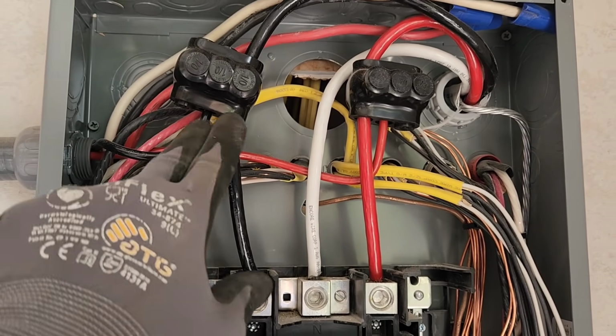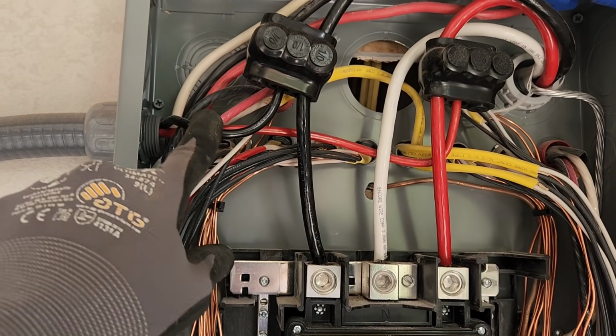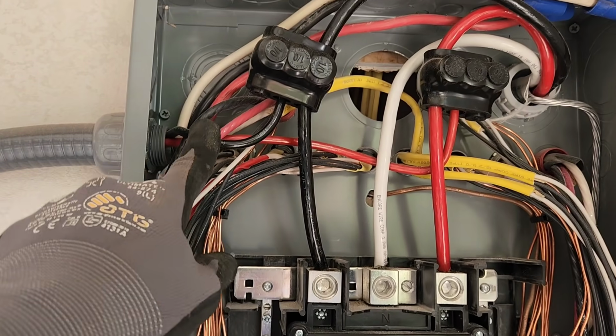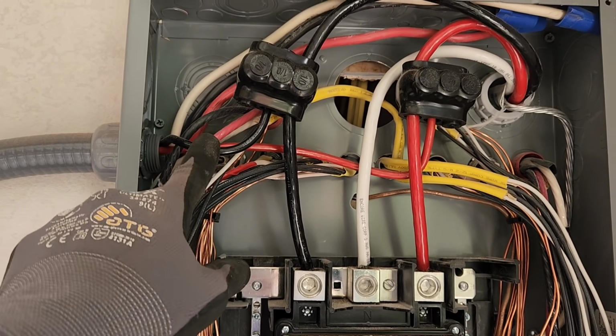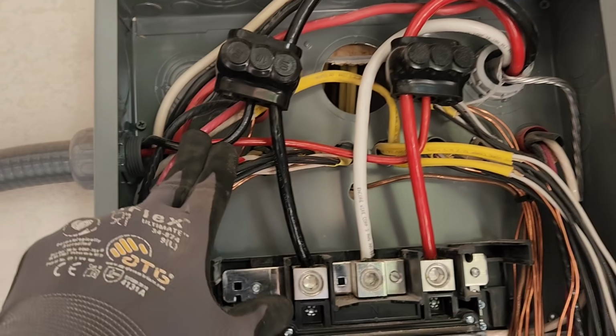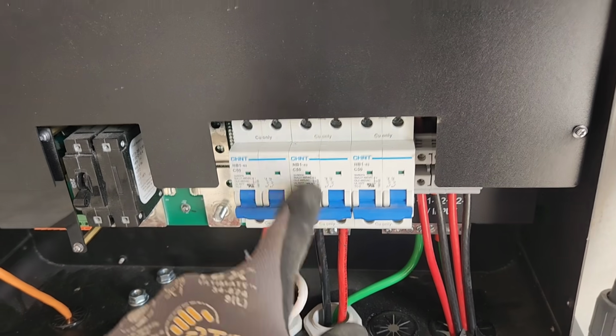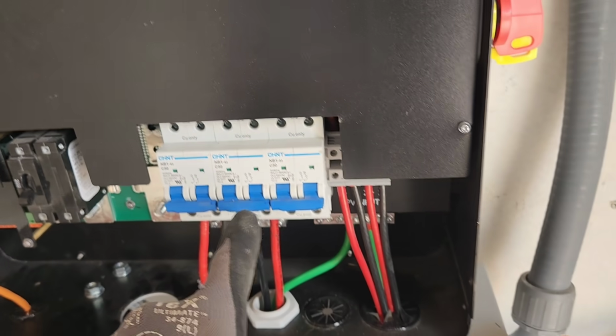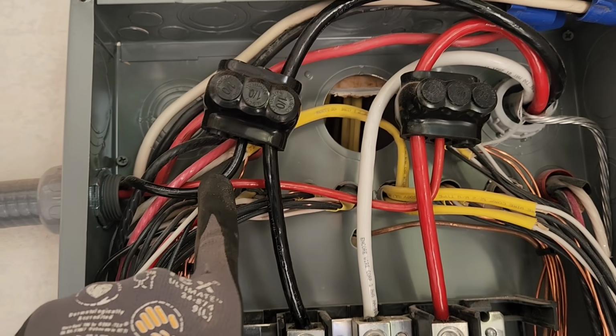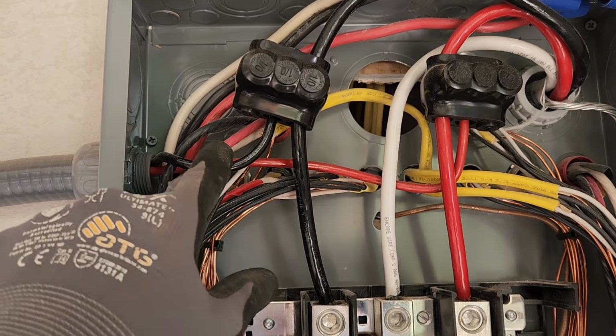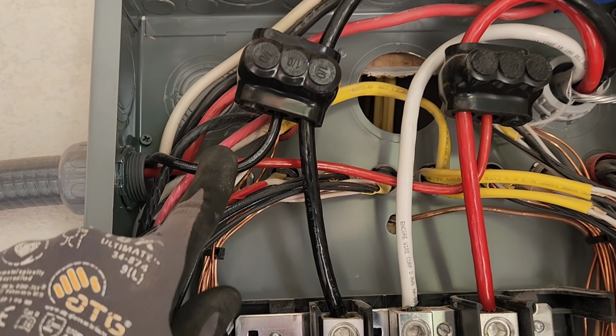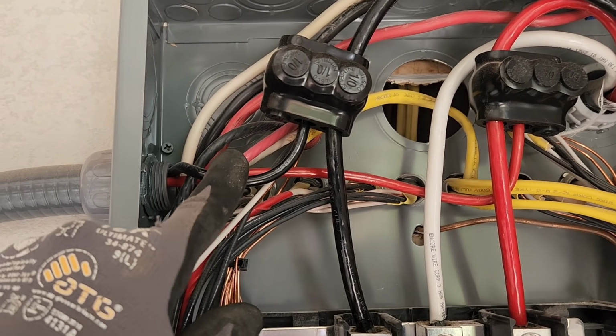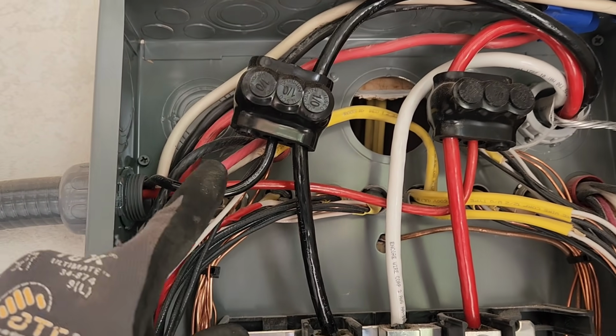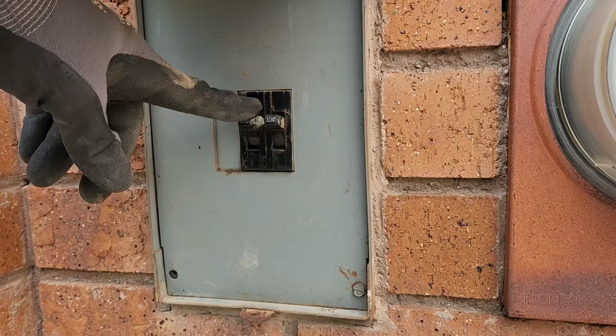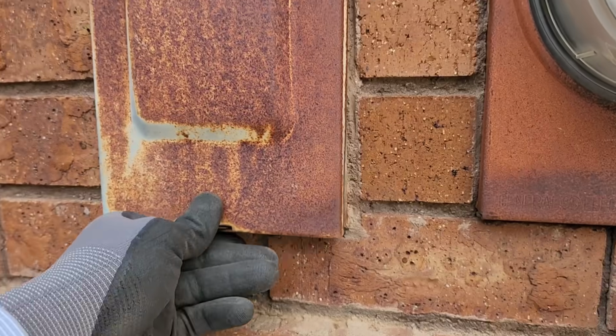Right now, this wire that hooks into the inverter is number 6 American wire gauge, which I believe can support something like 70 amps. I've got a 50 amp breaker here, so if it pulls more than that, this should trip. However, since I'm connecting this wire to 2 inverters, I'm going to upgrade it to number 4 wire, which should support 100 amps, and that'll also be protected by the breaker upstream near my meter.